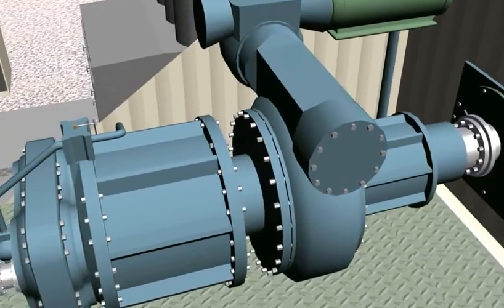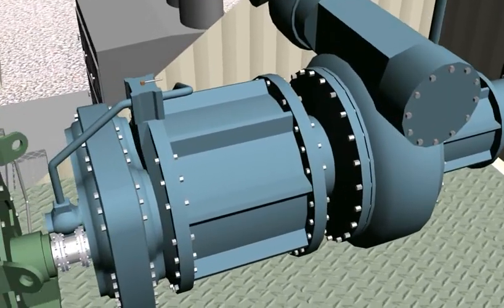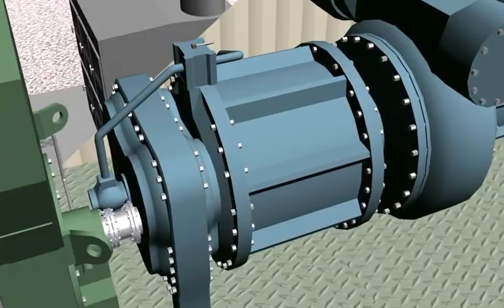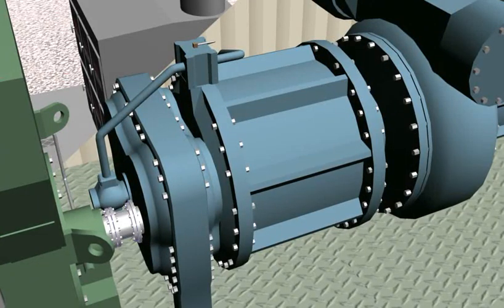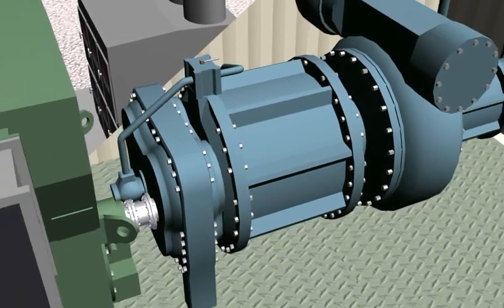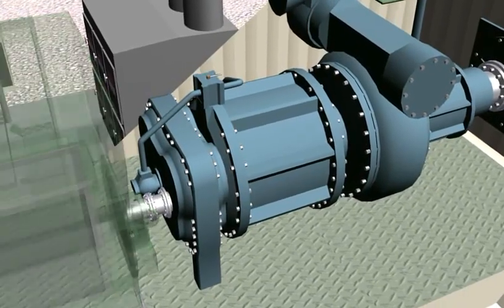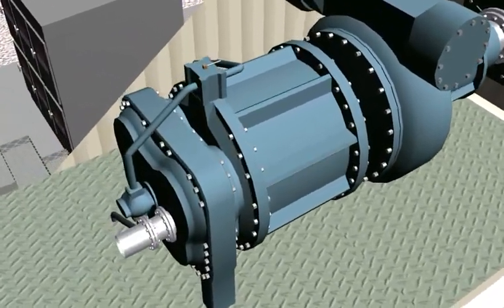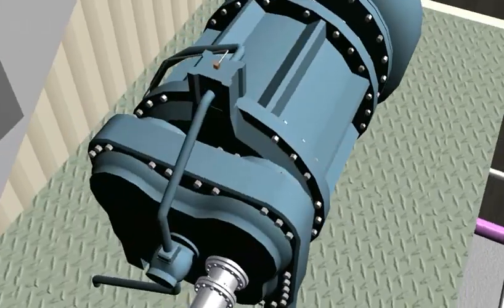Since the starting motor does not have the low end torque needed to begin rolling the rotor, a hydraulic torque converter is used to accelerate the rotor up to 2400 RPM. The torque converter uses turbine lubricating oil for lubrication and as the working fluid.